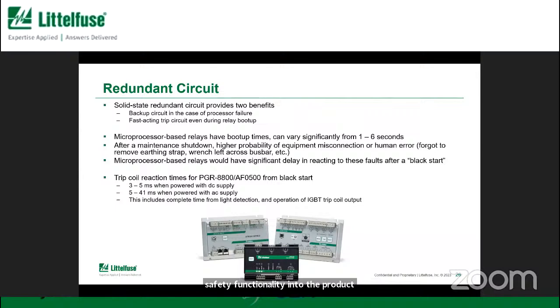Now, I know there's a lot of words on this page, but the point I want to make here is, I mentioned that backup redundant circuit inside the relay, but there is a second benefit that provides. That backup circuit is solid state. So when you first power on the relay, the microprocessor circuit does take a little bit of time. So most relays will take maybe a half second, 2 seconds, 3 seconds.